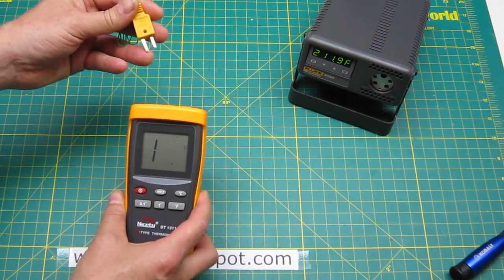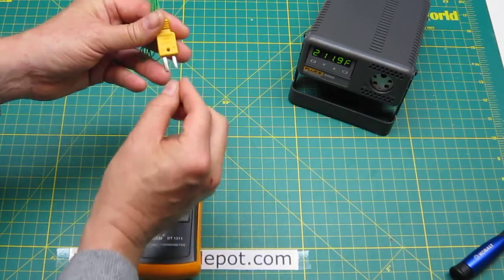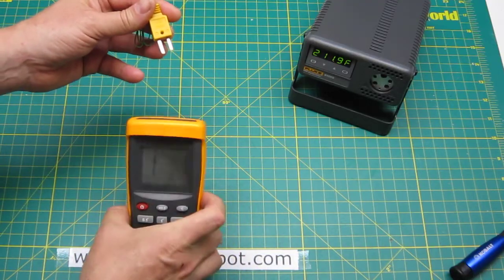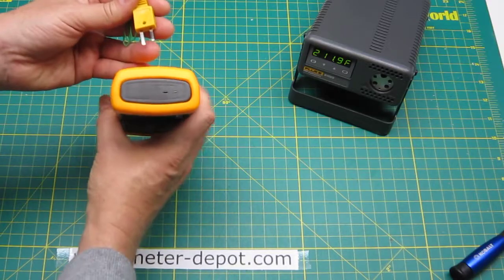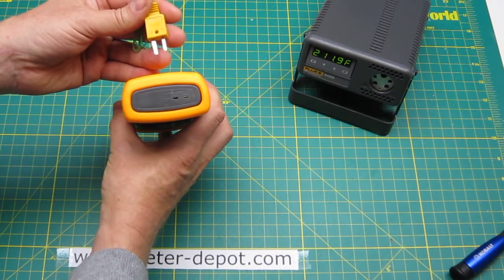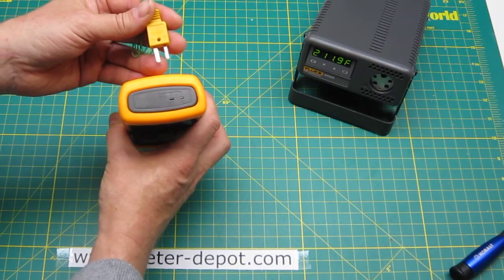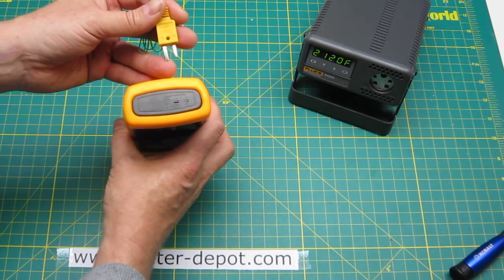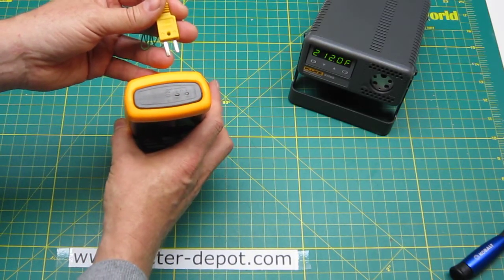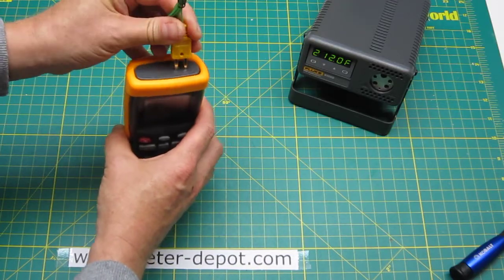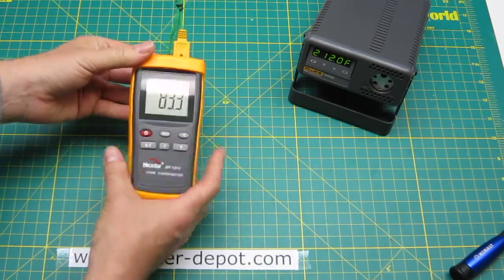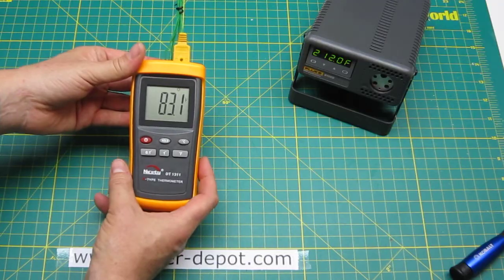If you look at the plug of the thermocouple you will notice you have a narrow blade and a little bit of wider blade and you need to be very careful to insert it correctly at the top. They can be inserted the wrong way. The smaller blade is the plus, the wider blade is the minus contact. Insert it and the measurement starts immediately.